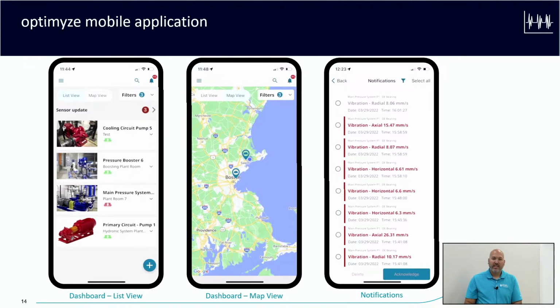So if you just log into the Optimyze app, you're seeing everything's green, maybe that's as far as you go, right? You got your peace of mind, you're seeing everything is green, you're good. However, if you're seeing something red or yellow and you want to investigate it more, you should have some alarms. So you see a little bell icon in the top right corner. You would click that and it's going to tell you exactly what went wrong. So you'll see vibration and what axis, the specific vibration reading, date and time associated with that to take a look at. However, you can investigate a little bit more.